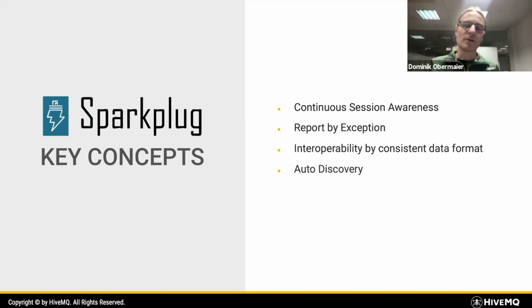What Sparkplug adds here is it utilizes MQTT by report by exception. Every device, every application just updates the value and pushes the data to the broker. The broker makes sure that everybody interested in the data gets the data point. This is a paradigm shift, because now you only send data if you need to, and you don't need to poll all the time and waste compute power and bandwidth.